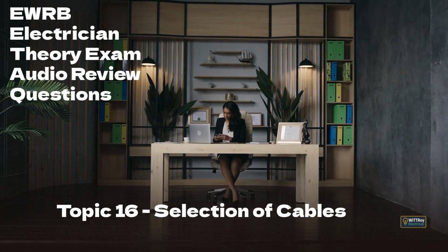Correct answer is option B. Prospective short-circuit current is the fault level available from the supply and installation impedance. It is used to check breaking capacity of devices and short-circuit thermal withstand of cables.